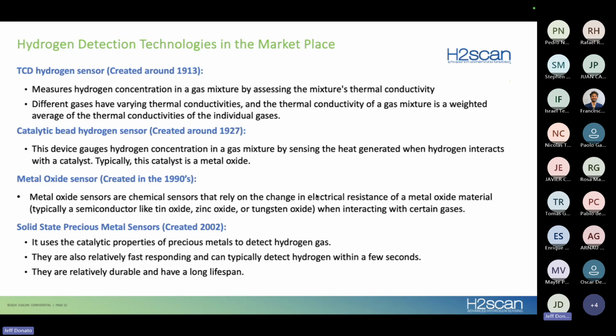And the last one was created in 2002 by Sandia Labs in the U.S. It was a solid state precious metal sensor. Some of you might know it as palladium sensors, and it uses the catalytic properties of a precious metal to detect hydrogen gas. They're fast responding, and they have a very long lifespan. Of course, being a precious metal, the lifespan is infinite. They don't wear out. They can become contaminated by the outside environment, such as dust and debris that may be in the site, but the sensor elements themselves typically last a very long time.